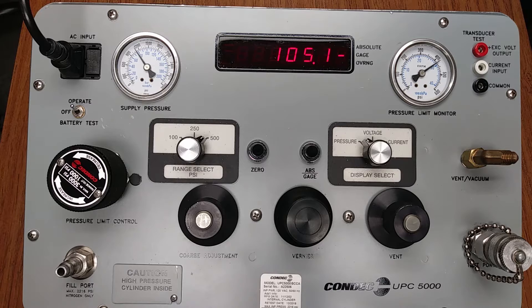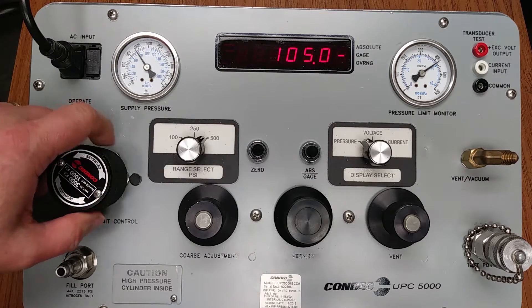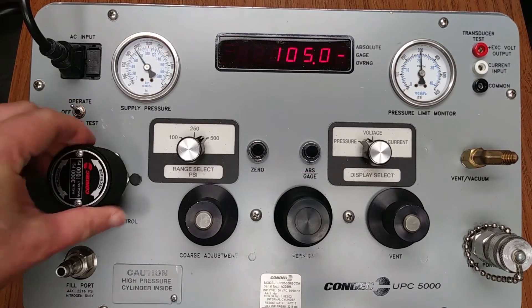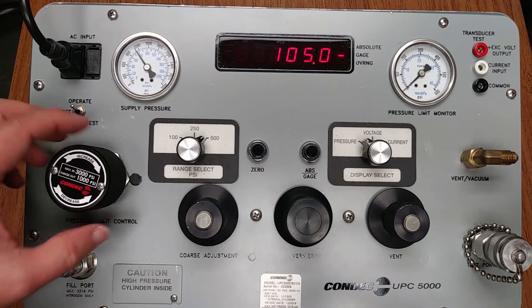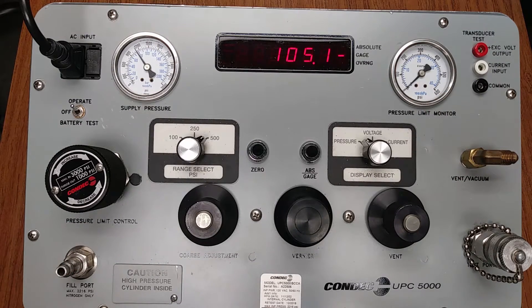Once all required target values have been reached, the calibration process is complete. The pressure limit control knob is to be rotated counterclockwise until the analog gauge returns to zero. We are now rotating counterclockwise — the pressure limit control is now at zero. The vent valve is to be opened by turning the knob counterclockwise slowly until the LED display has returned to zero.